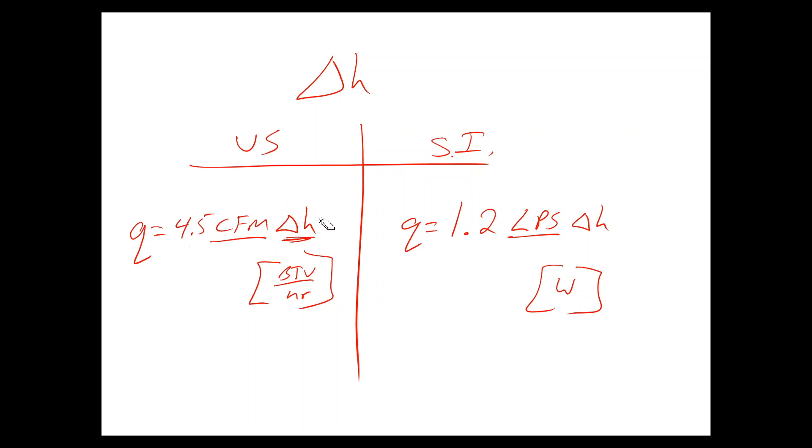So, in the U.S., we have CFM cubic feet per minute times 4.5 times the delta H. We get that from the psych chart, okay. And, in the International, same thing. We get the delta H from the psych chart. And, we can plug it right into this equation for Q. Hopefully, this helps you understand heat transfer and how the psych chart factors into that process. Catch you next time.